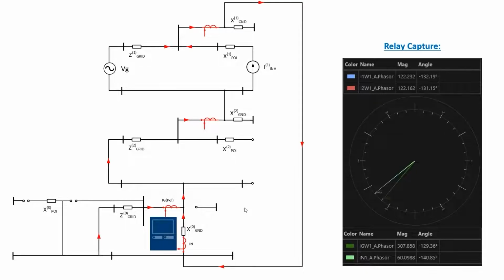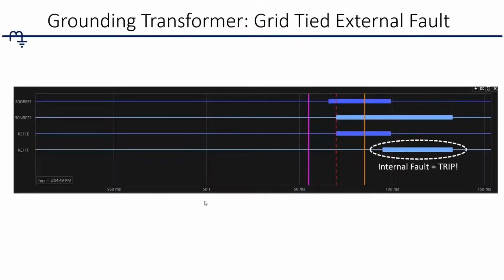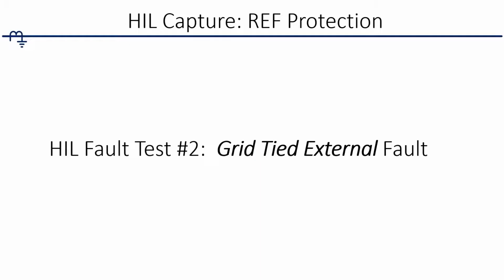So for you P&C engineers, I took the time to draw out the positive, negative, and zero sequence networks. I won't focus too much on that. It's kind of a vision test a little bit to go through each one of them. But I grabbed the phasor quantities from the relay, and here's what we got. As you can see, the angles, as we expected, are pretty narrow, indicating that it was an internal fault. And the relay did trip, which was good. REF1F, which is what the relay calls a forward fault, indicates that the fault is inside of the transformer. It correctly identified it as an internal fault, and it did trip. So it did operate for this internal fault.